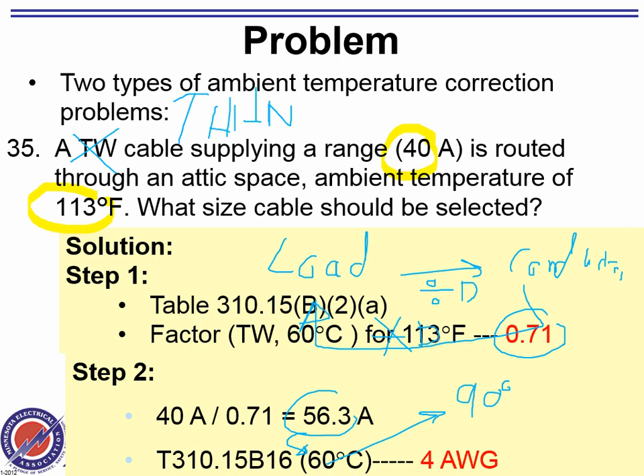We didn't say anything about continuous here. It's under the 60-degree column for two reasons. Number one, because of the TW. For the THHN, it's because it's less than 100 amp, and we have no idea what the lugs are. Yes. If it's less than 100 amp, regardless of what your installation is, under normal operating condition, no derating, you're stuck with the 60-degree column.